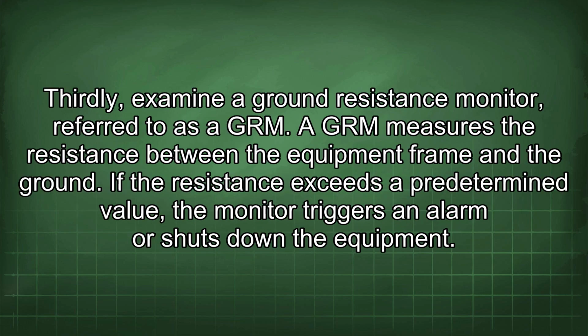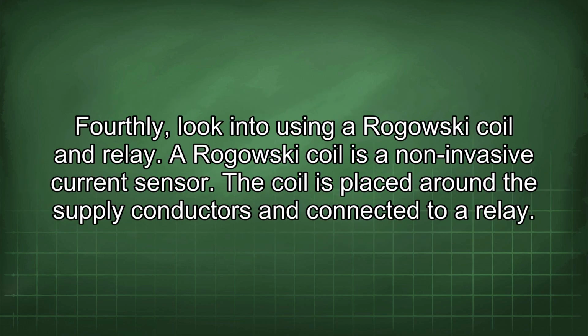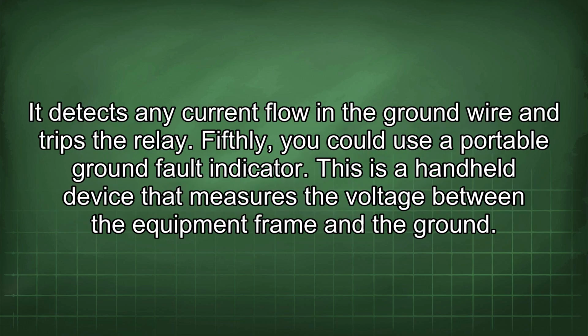Thirdly, examine a ground resistance monitor, referred to as a GRM. A GRM measures the resistance between the equipment frame and the ground. If the resistance exceeds a predetermined value, the monitor triggers an alarm or shuts down the equipment. Fourthly, look into using a Rogowski coil and relay. A Rogowski coil is a non-invasive current sensor. The coil is placed around the supply conductors and connected to a relay. It detects any current flow in the ground wire and trips the relay.